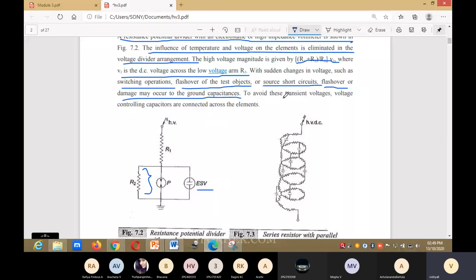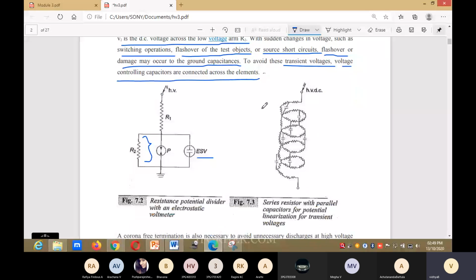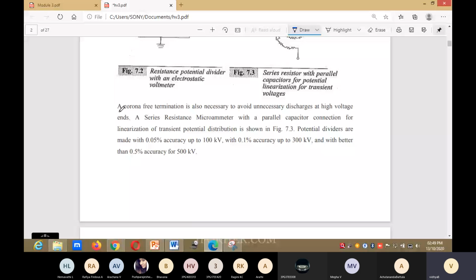To avoid these transient voltages, voltage controlling capacitors are connected across the elements. A corona-free termination is also necessary to avoid unnecessary discharge at high voltage ends.